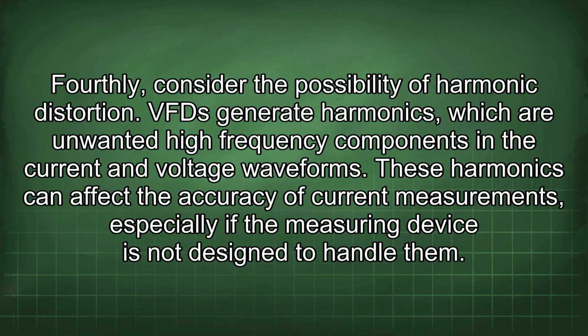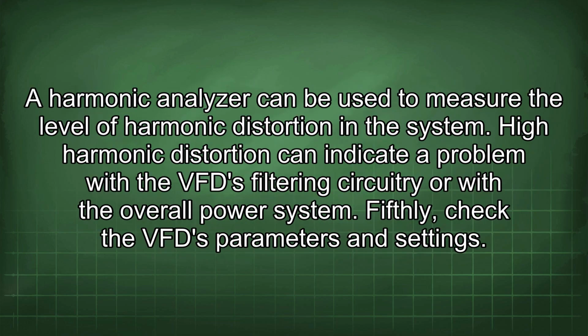Fourthly, consider the possibility of harmonic distortion. VFDs generate harmonics, which are unwanted high-frequency components in the current and voltage waveforms. These harmonics can affect the accuracy of current measurements, especially if the measuring device is not designed to handle them. A harmonic analyzer can be used to measure the level of harmonic distortion in the system. High harmonic distortion can indicate a problem with the VFD filtering circuitry or with the overall power system.